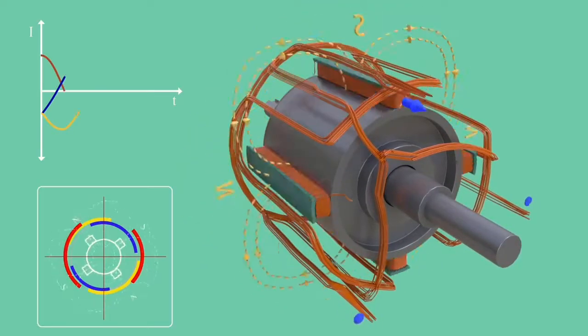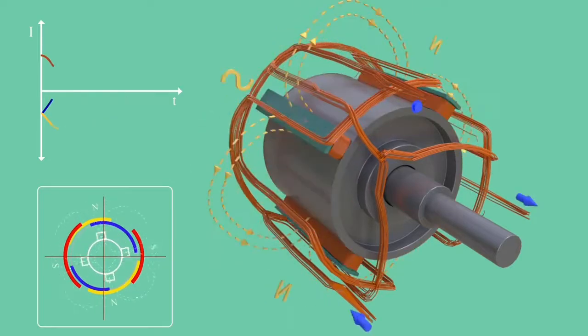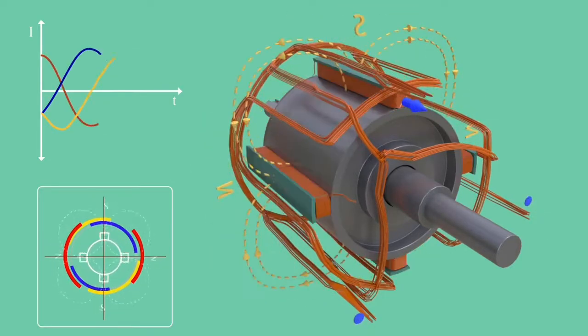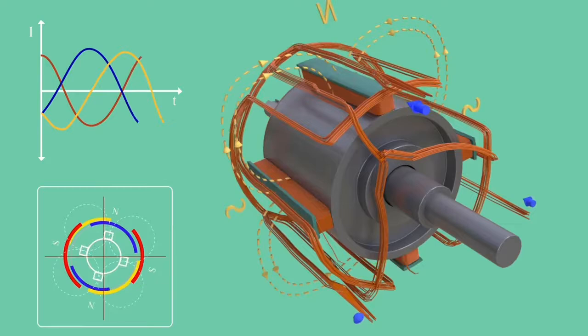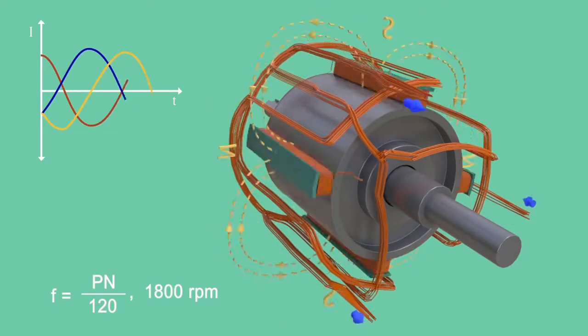It is clear from the equation above that in order to produce 60 hertz electricity, a four pole rotor should run at a speed of 1800 RPM. Such huge RPM will induce a tremendous centrifugal force on poles of the rotor and it may fail mechanically over time.